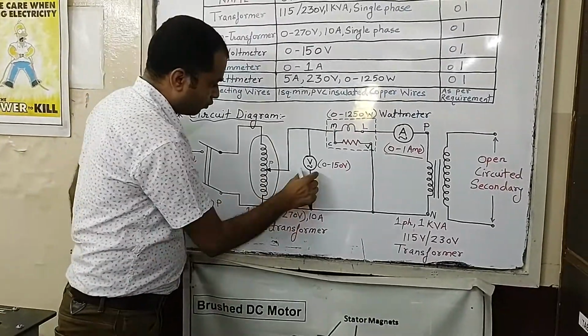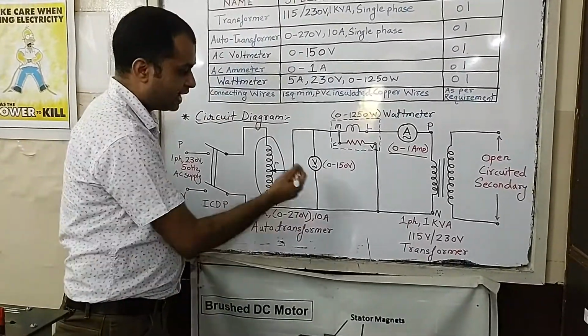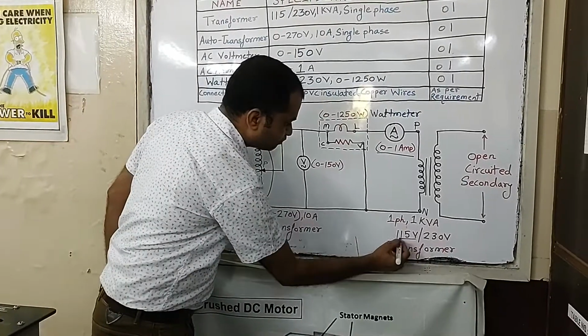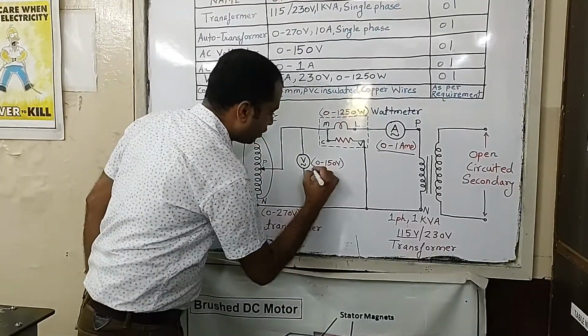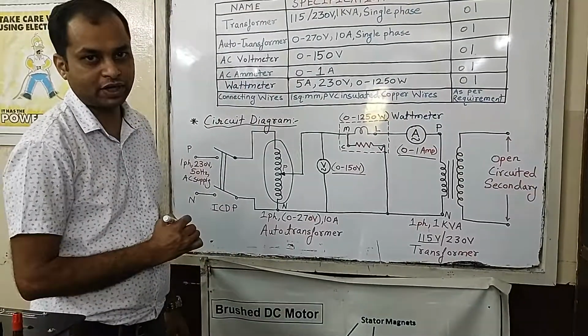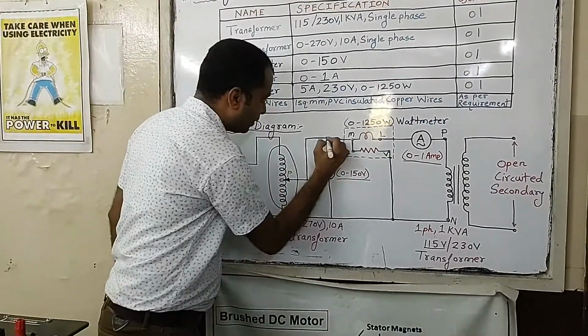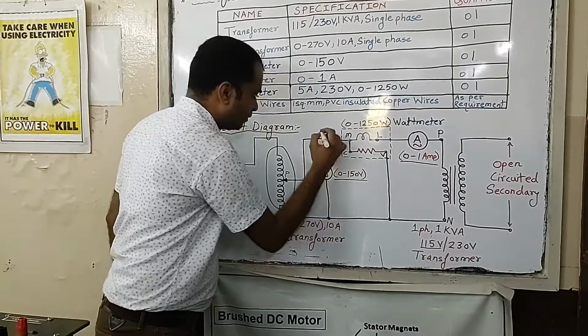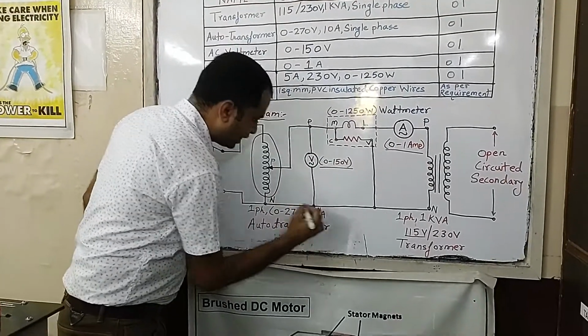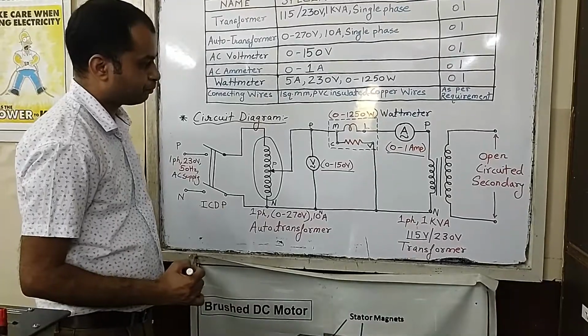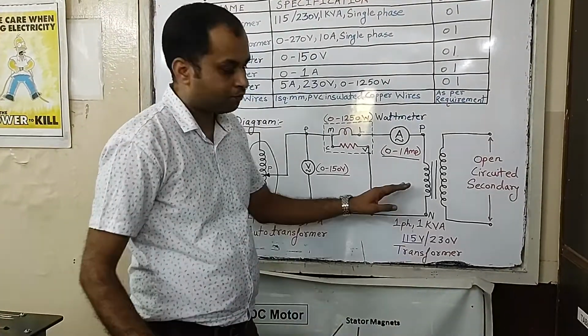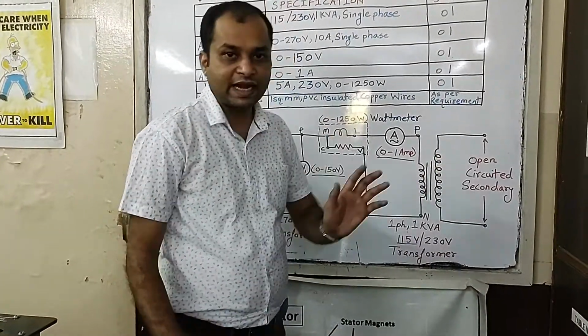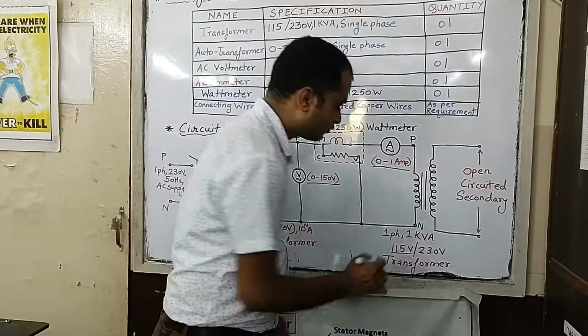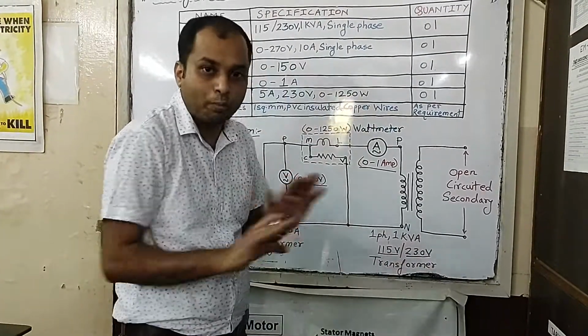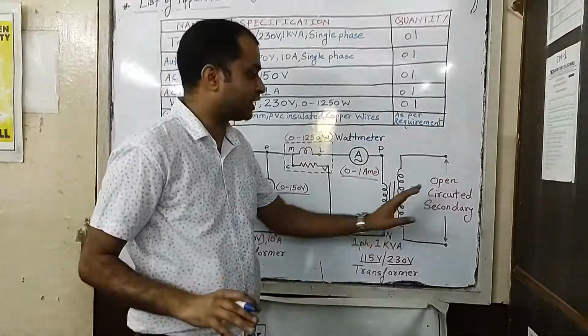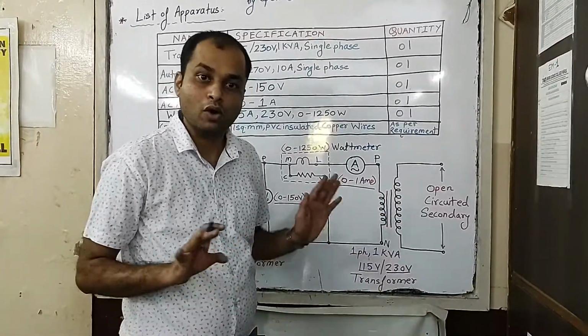So to measure the voltage across the primary side, as it is of 115 volt, we will use a voltmeter of the range of 0 to 150 volt in parallel between the phase and neutral. So this will measure the voltage across the primary side. Now for this experiment we have to keep the secondary winding, which is of 230 volt, open. We don't have to make any connection across the secondary winding, we have to keep it open circuited.